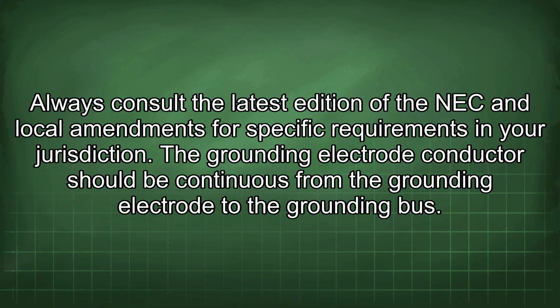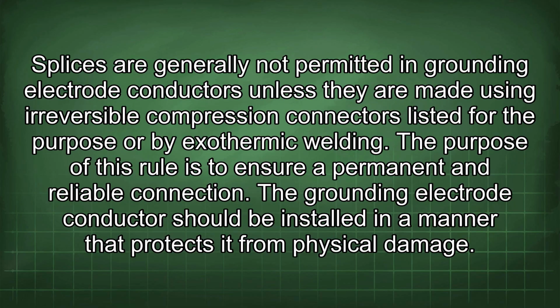The grounding electrode conductor should be continuous from the grounding electrode to the grounding bus. Splices are generally not permitted in grounding electrode conductors unless they are made using irreversible compression connectors listed for the purpose or by exothermic welding. The purpose of this rule is to ensure a permanent and reliable connection.